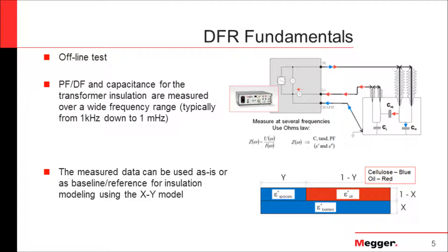Let's start from the fundamentals. Dielectric frequency response is basically an offline test. The transformer has to be de-energized, disconnected, and fully isolated from the line. You will be testing only your transformer, which has to be discharged and properly isolated. You will follow any safety and security measures or recommendations applied in that substation, utility, or wherever you are running the test.